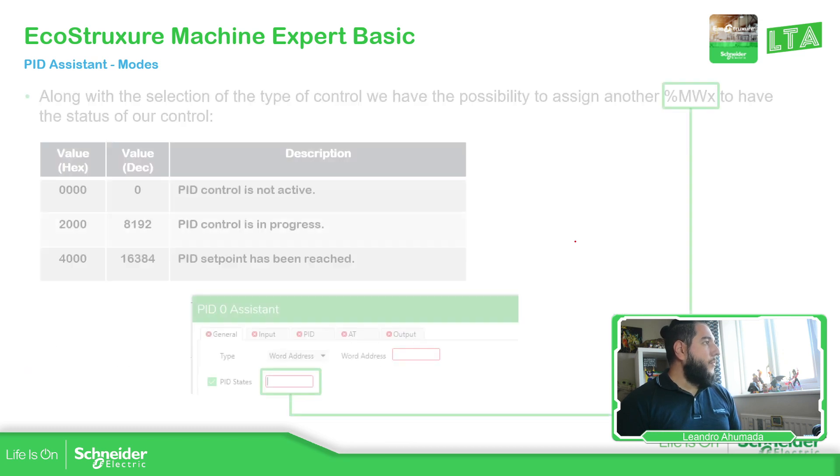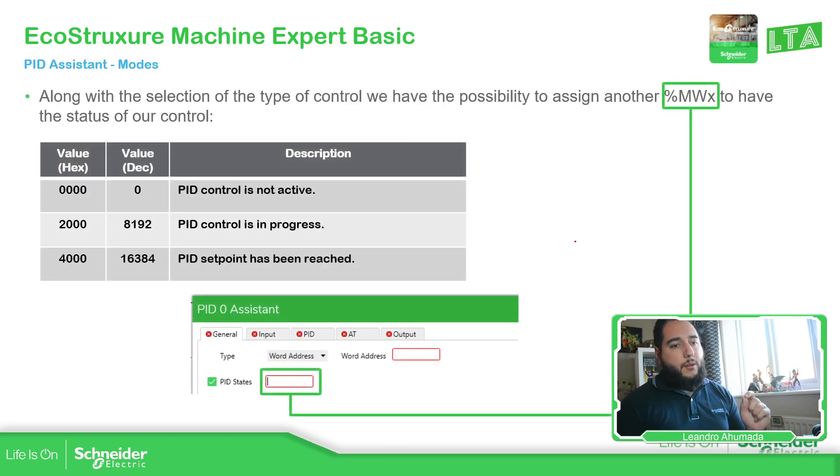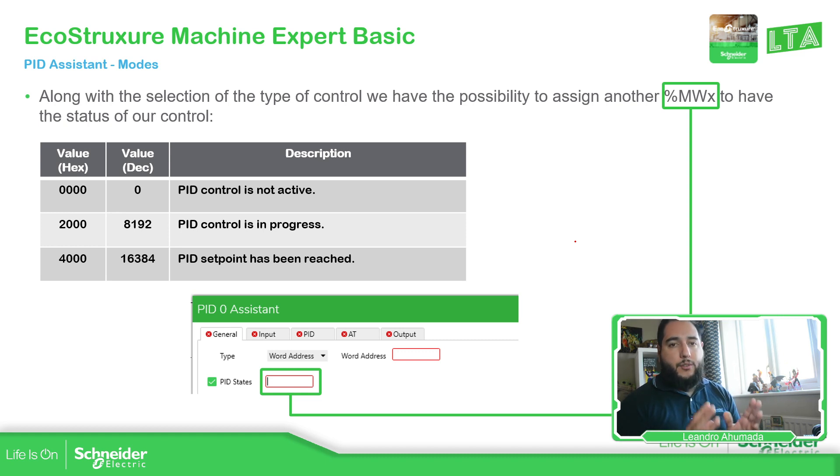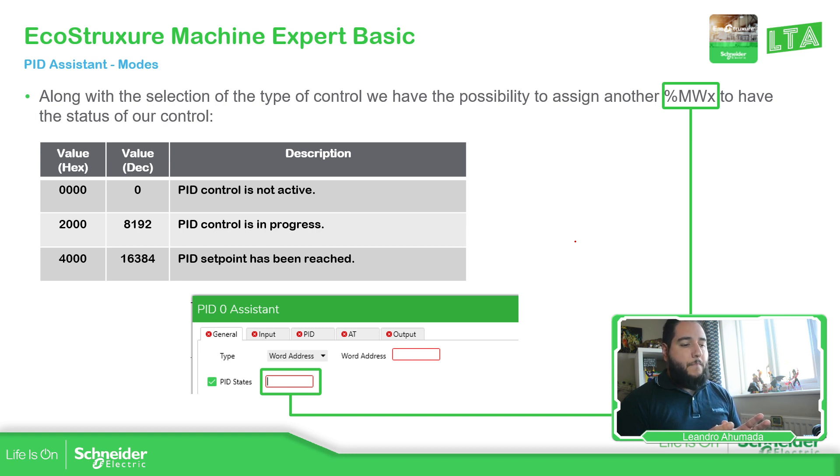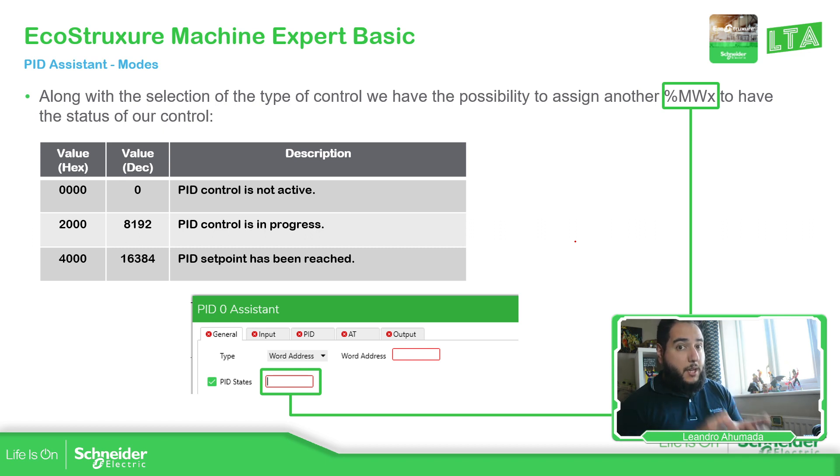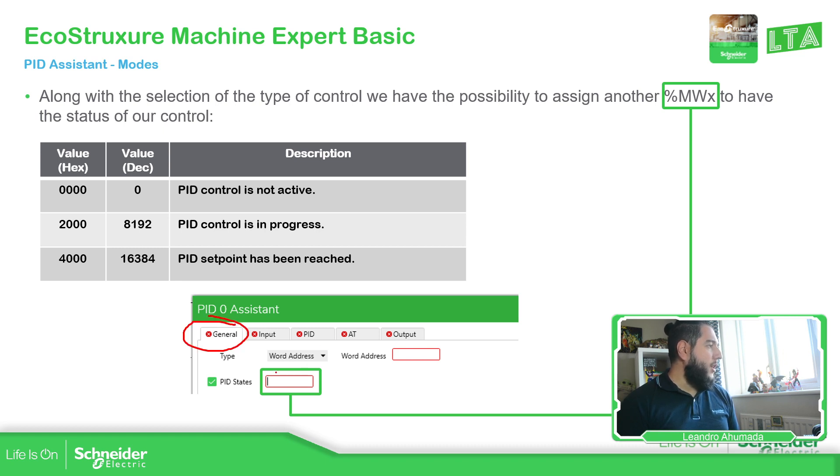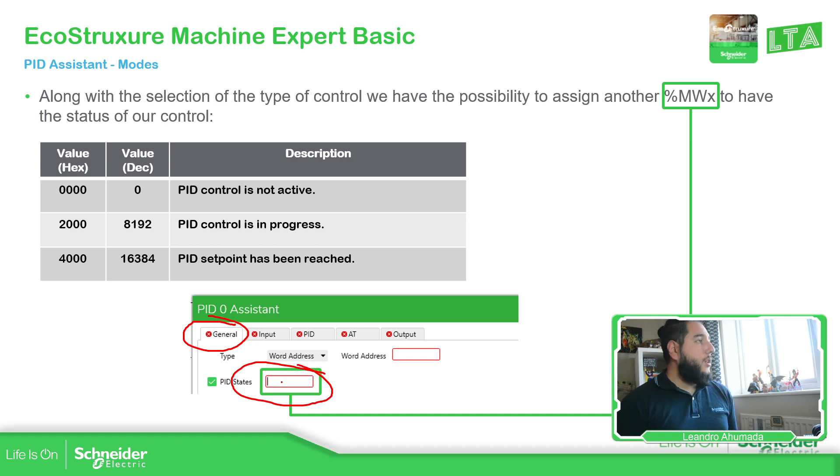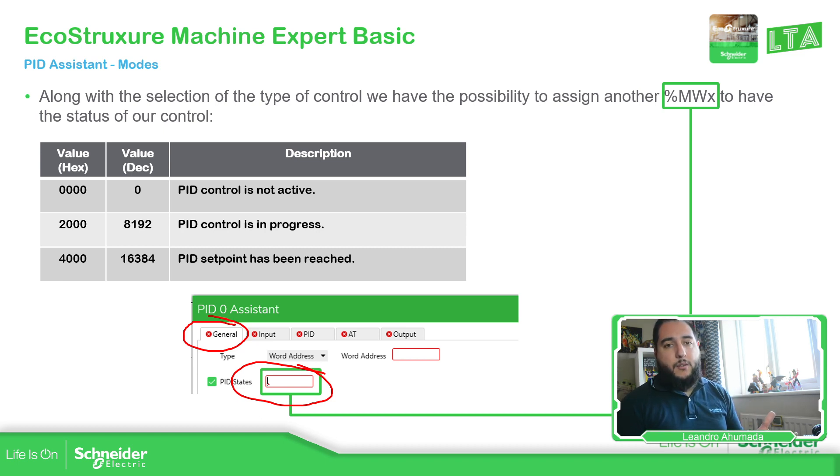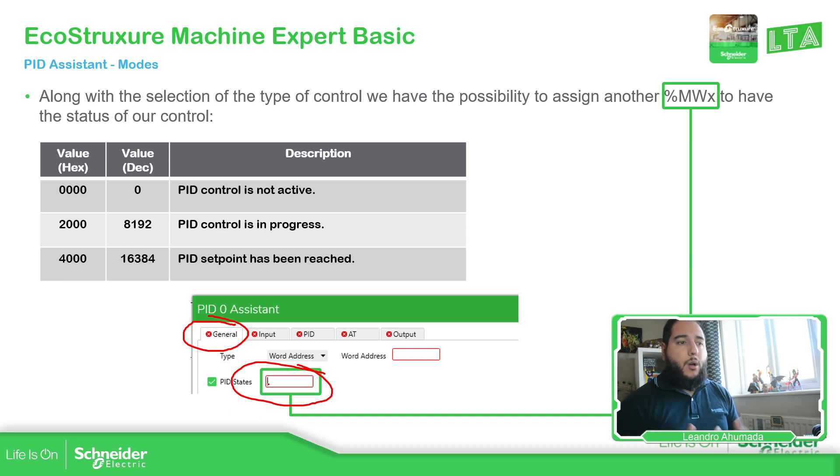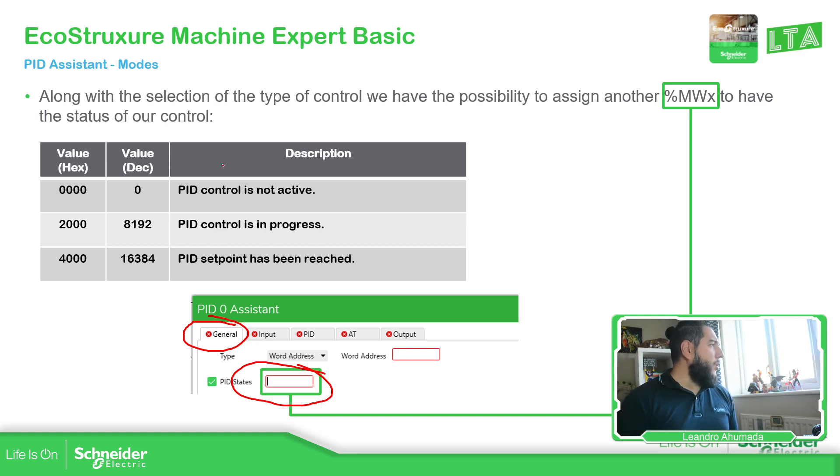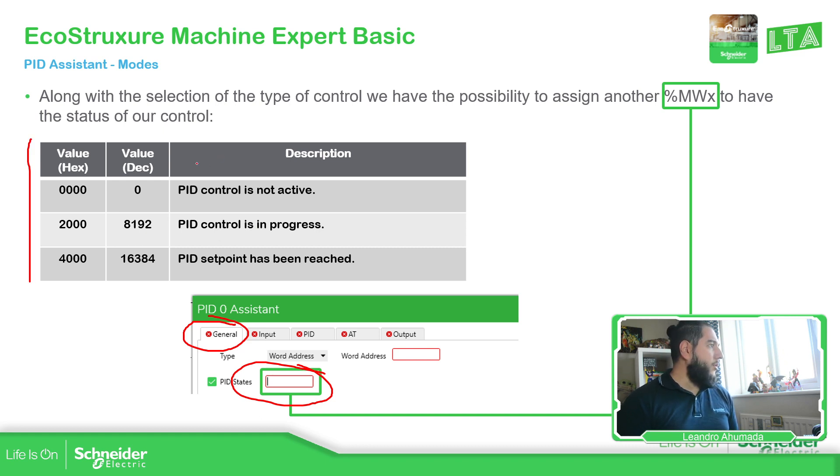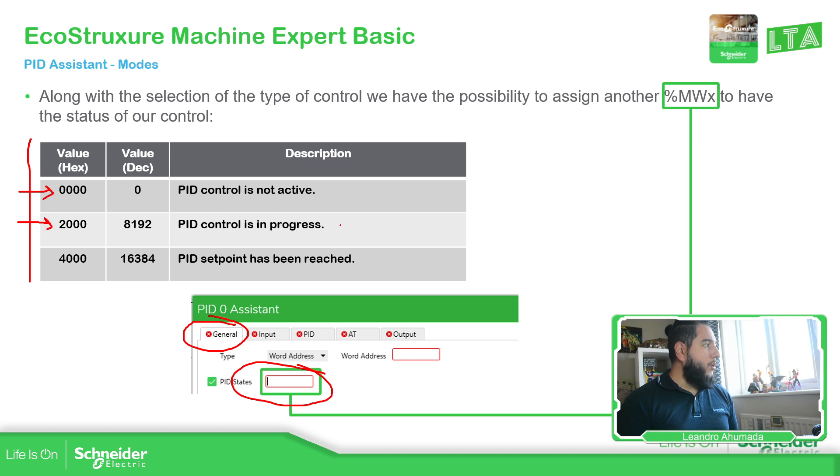Something important here for all the modes is that even if I select word address or PID or auto tuning, we can link the actual process or the state of the status of the PID with a variable. So if we go to the General tab, we can link a %MWx variable to this variable PID state. So we can see further information about what we are doing. If we have an error on the configuration or if the PID is not activated or something.